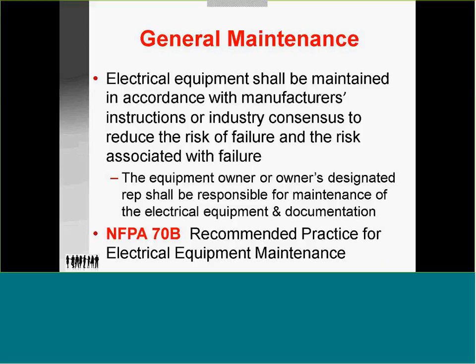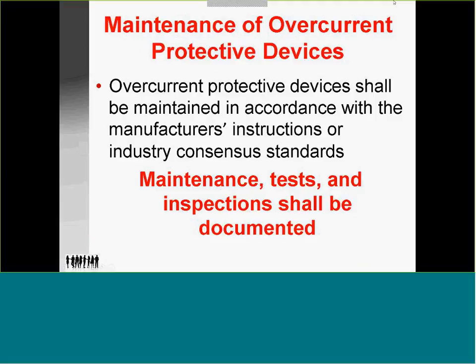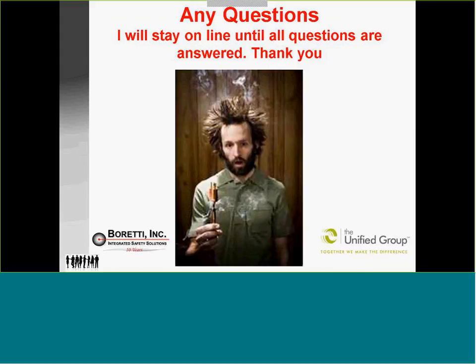Now, the owner or owner's designated rep shall be responsible for maintenance of the electrical equipment, and this is where they bring in 70B. It's recommended practices. Maintenance. All devices shall be maintained in accordance with the manufacturer's instructions. Maintenance, tests, inspections shall be documented. They know that they're clearing on time. If they don't clear within a prescribed time, they have to be replaced.